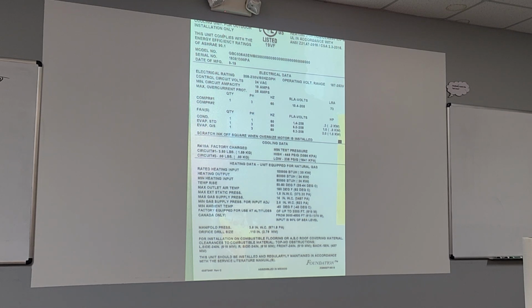Yep. Wow. So I had to go through and correct a few things on the profile because it did not read everything exactly right. Temperature rise range is 50 to 80. AI read it as 20 to 50. Orifice size was not right. But it's handy. I mean, it read the model number, serial number, and everything. That's huge right there. Got the refrigerant charge right. BTU ratings on the heating side were all set. So, as Reagan said, trust but verify.